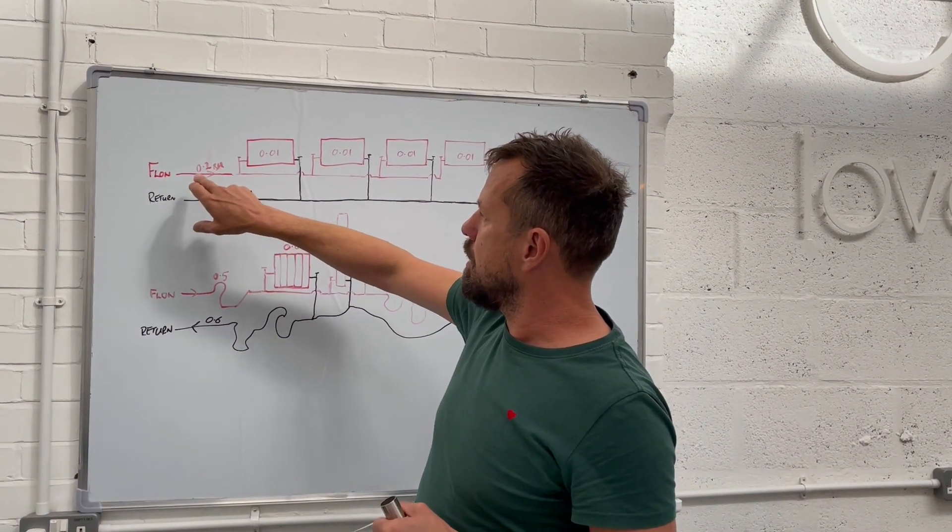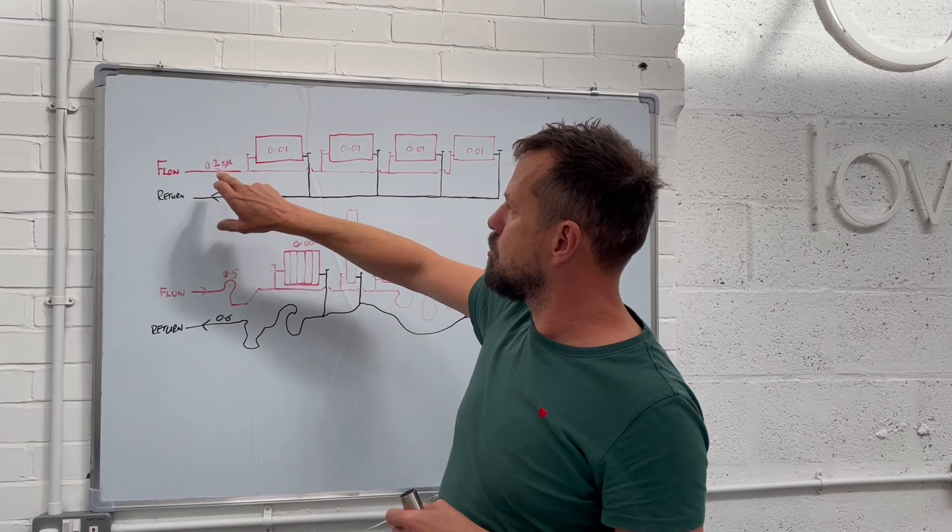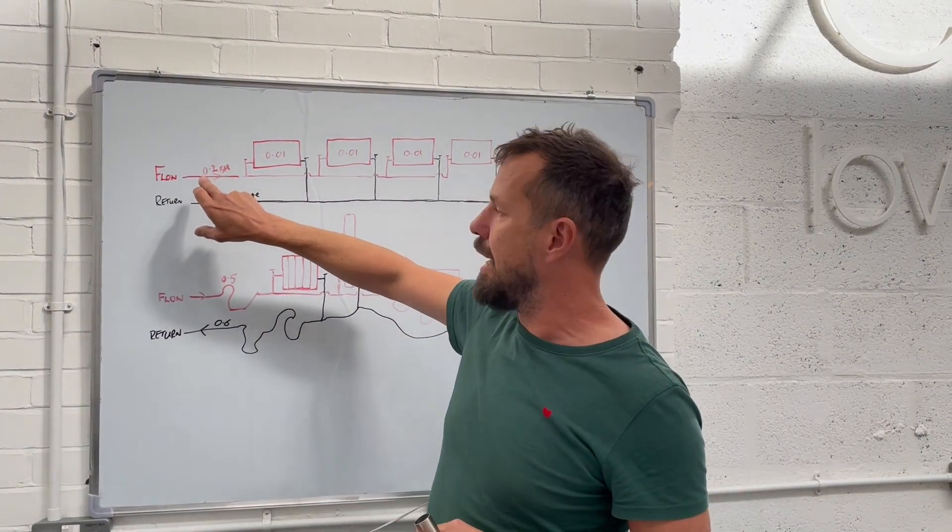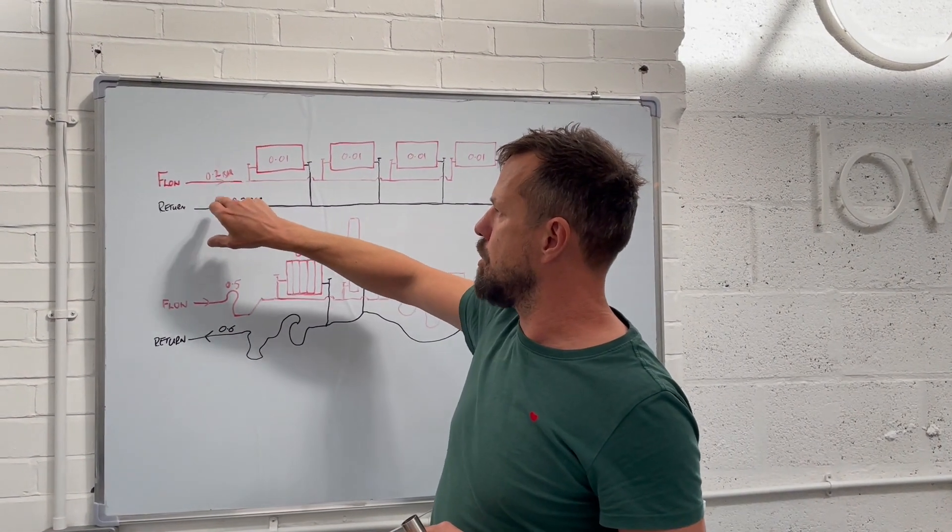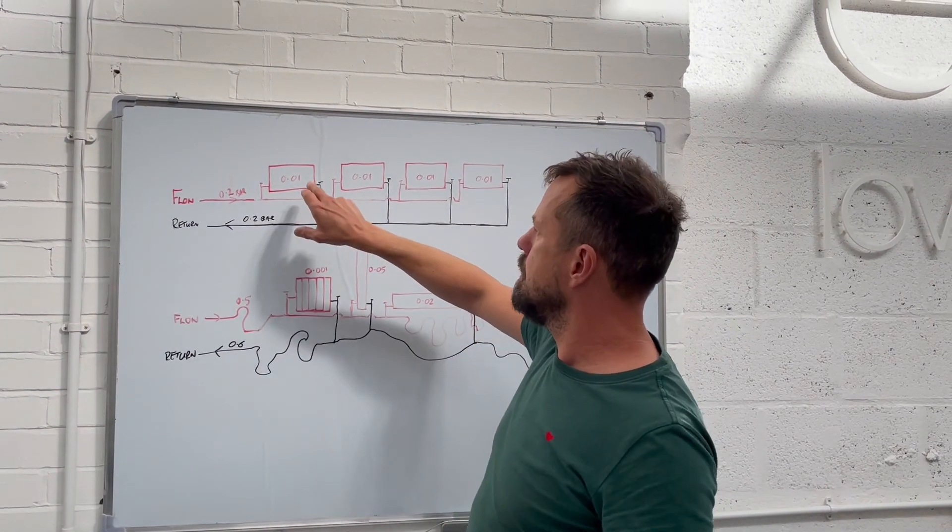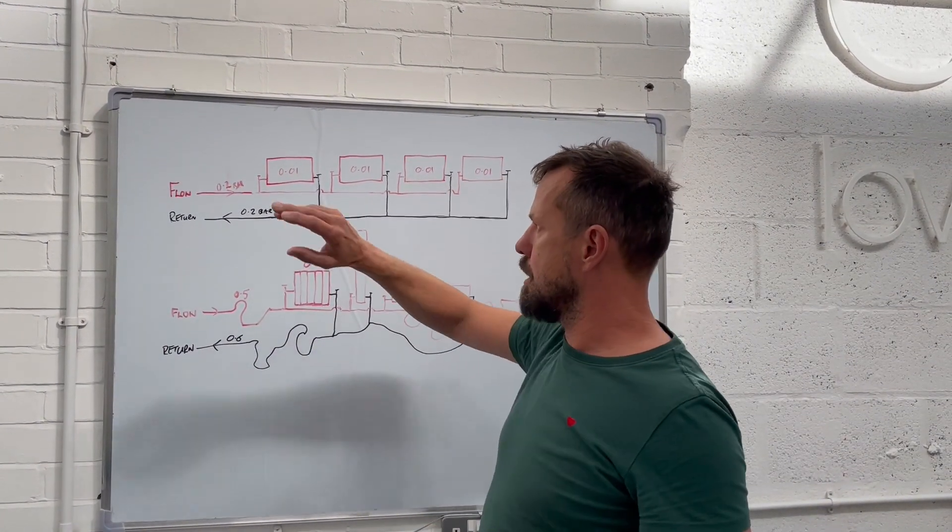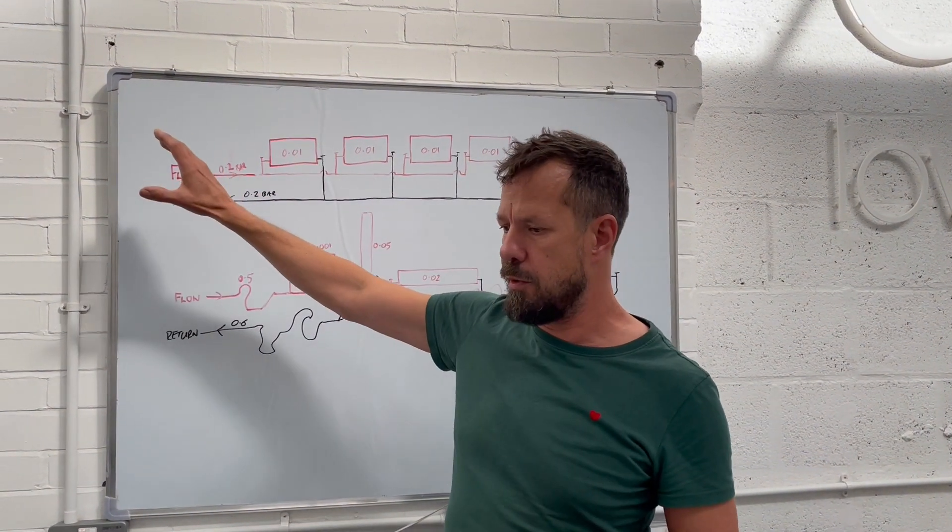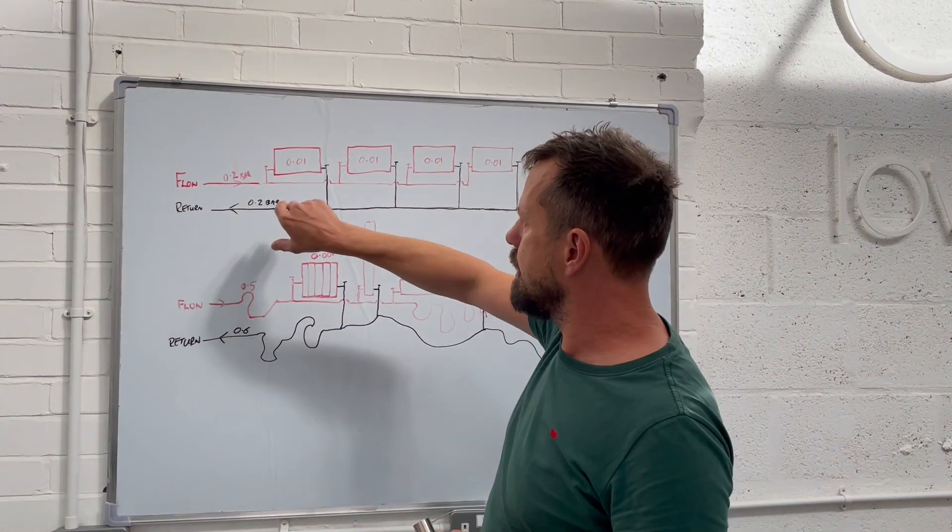On the flow, you have the pressure drop of the pipework added up in total is 0.2 of a bar. Each of these identical radiators is 0.01 of a bar. So that's great. We can account for that when we size our pump. It's really easy.